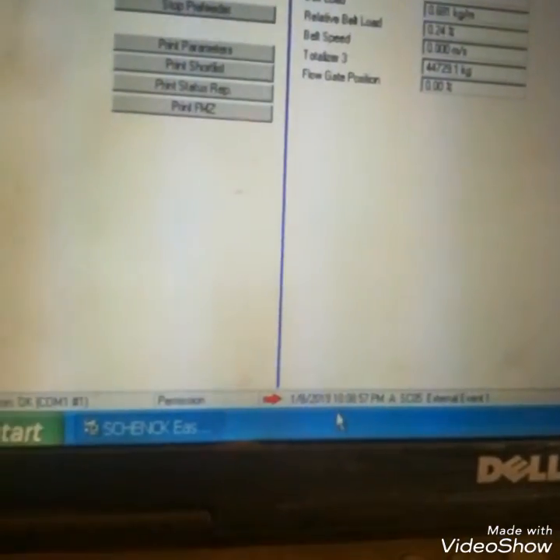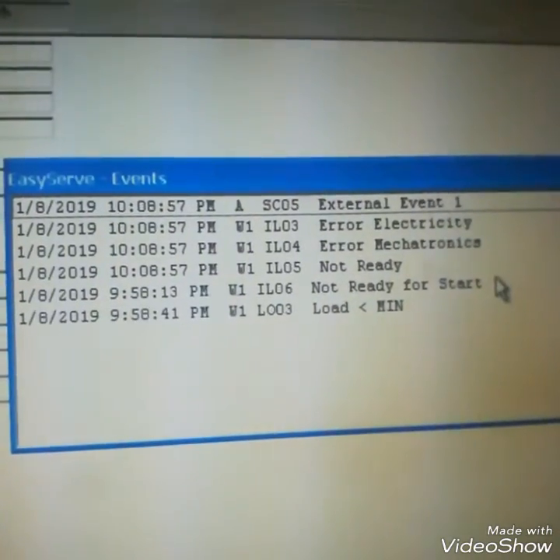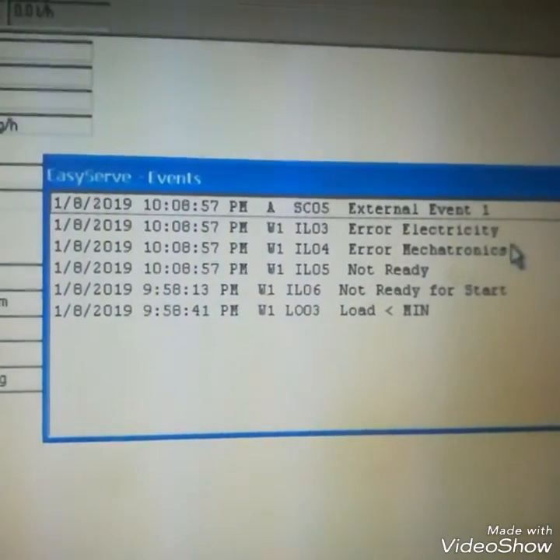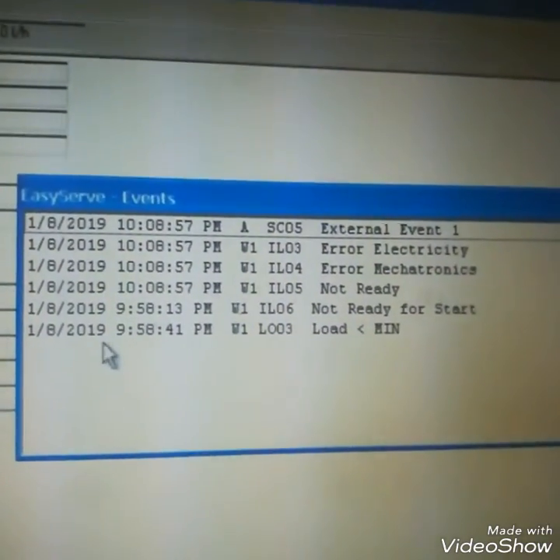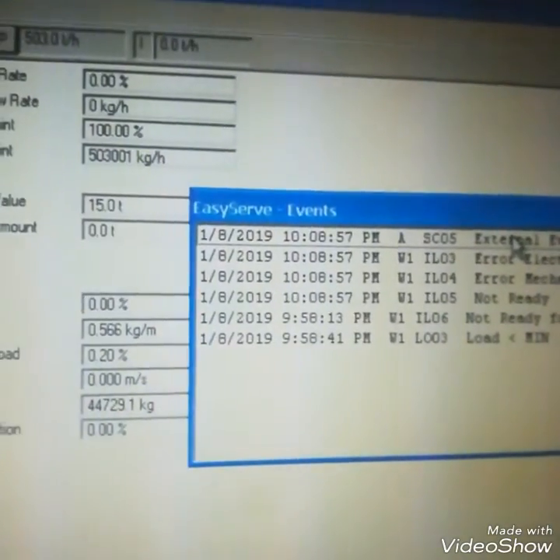As it is showing an alarm, this I am showing you, this is an alarm. I will reset it from this clear event button, which is like a cross. Here you can see it's showing alarm with this red arrow. I will click it. If I want to know from where this alarm is generated, I will click it here and I will click it again. When I click it, it will open a new window. It will be the help window. It will show from which parameter this alarm is configured.